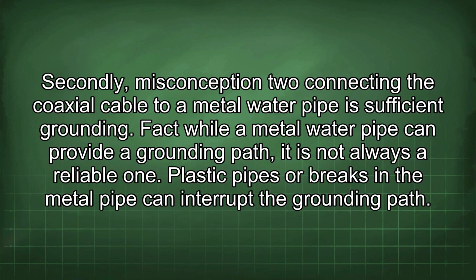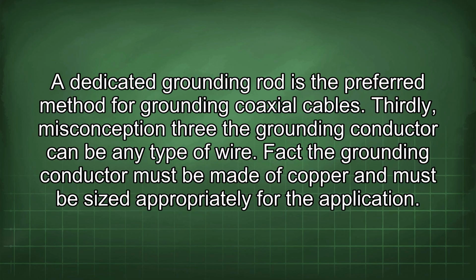Secondly, misconception 2: connecting the coaxial cable to a metal water pipe is sufficient grounding. Fact: while a metal water pipe can provide a grounding path, it is not always a reliable one. Plastic pipes or breaks in the metal pipe can interrupt the grounding path. A dedicated grounding rod is the preferred method for grounding coaxial cables.